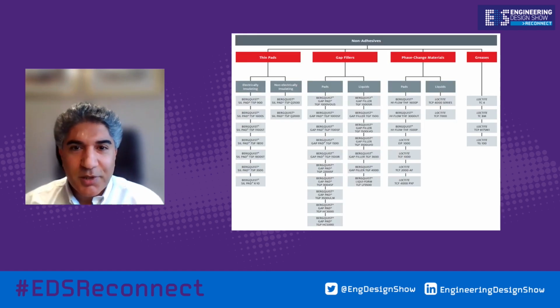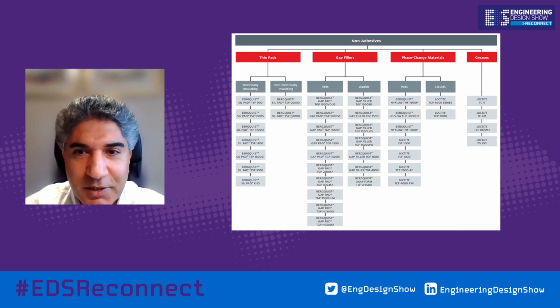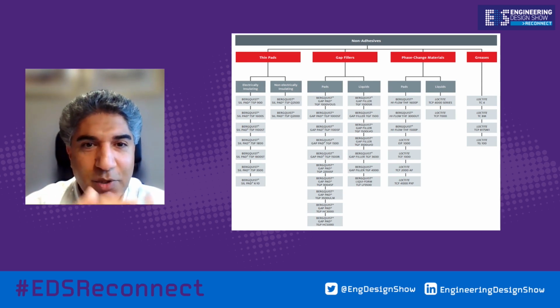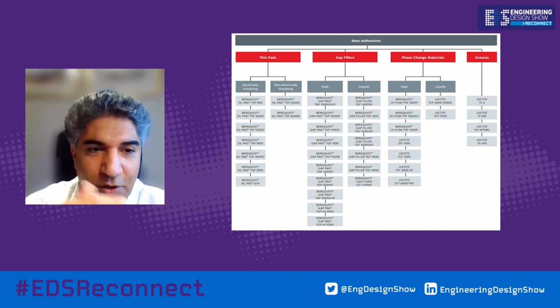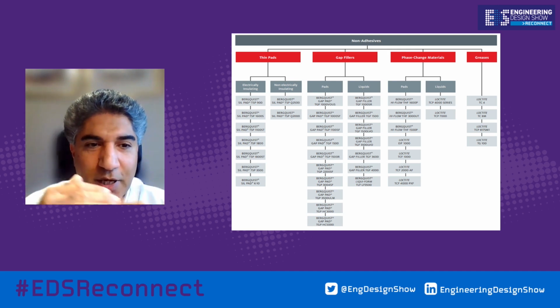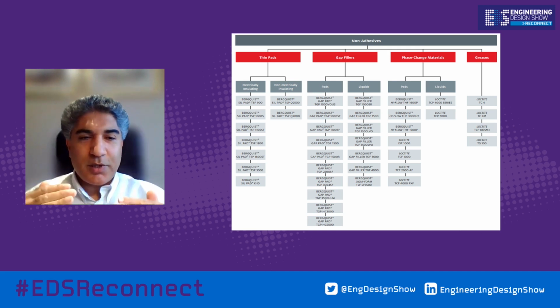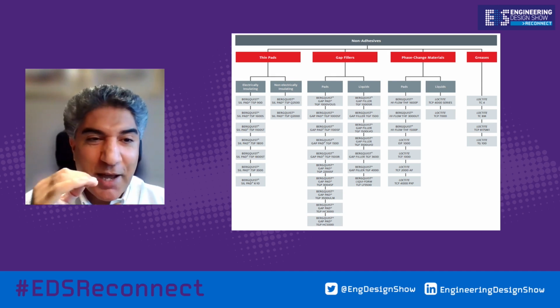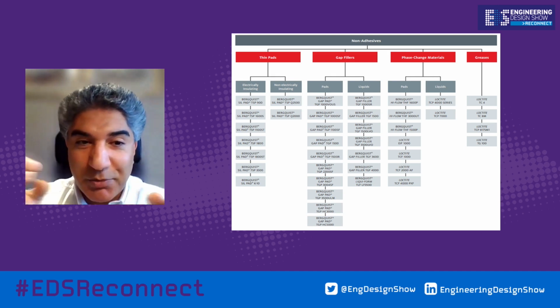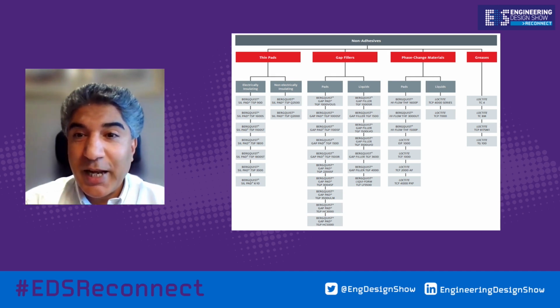Okay, as you can see from the Chomerics range, within the Bergquist range, we can help with the thermal thin pads, the gap pads, and the phase change material. Phase change materials, as I said earlier on, when heated, turn from a solid to liquid and push the air out, so you get good bond line thickness and attachment as well. And obviously greases for smears. I'm not a big fan of greases because if it heats up, it could spread, but they're better than air.